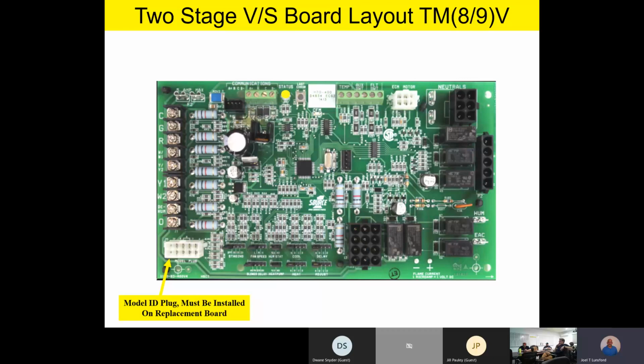And so please note that if you have to replace a board, be sure and take the model ID plug off the old board and snap it onto the new board. Then as soon as you power that new board up the very first time, the control board will know what size furnace it's hooked up to. Now, it's been a while since I've seen any replacement boards, but I'm thinking we ship more model ID plugs based on your need. But if you don't have extra model ID plugs, be sure and take the old model ID plug off the old board, snap it onto the new board, so that when you power it up the first time, the new board knows what size furnace it's hooked up to.